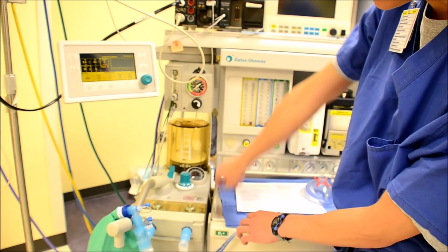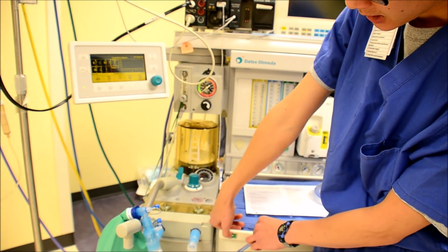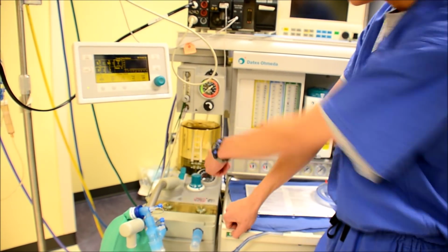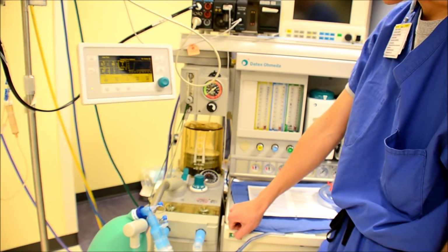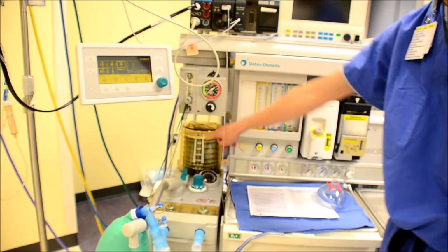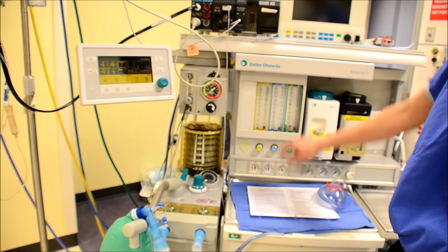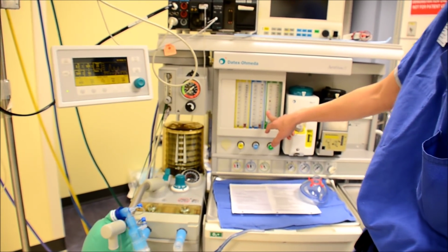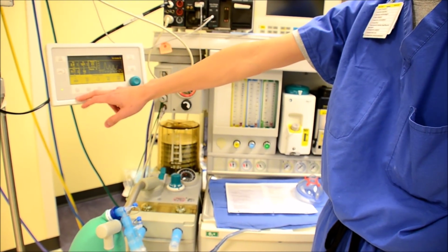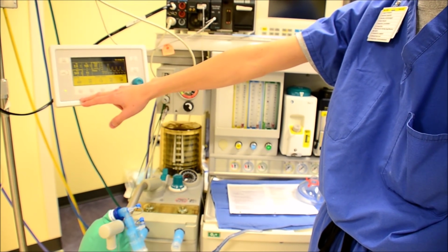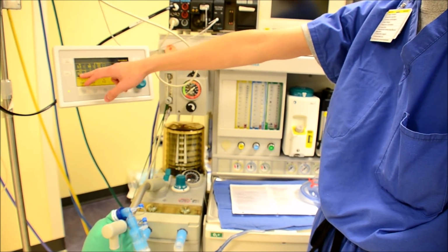So what you can do is, while you're waiting for this to rise, you can push your O2 flush button, and it'll make your bellows rise a little quicker. And let that set. So at low flows, you're checking to make sure the volume that you've set is being reached. So we can check the volume there.